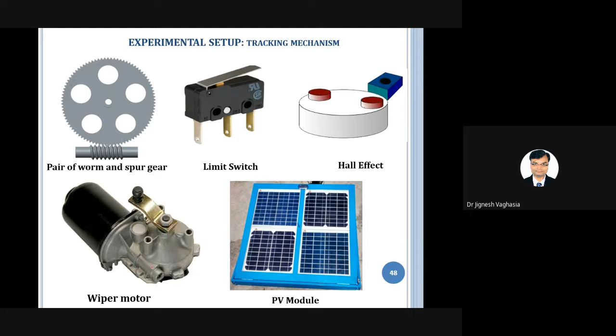Now how will it be rotating? With the help of worm and spur gear, our requirement is 1 degree rotation of the trough at every 4 minutes. So we require a timer, and 1 degree rotation of trough at every 4 minutes. And that's why we have taken a 90:1 spur worm ratio. So in that case, what happened? One rotation of the worm will make one tooth movement. Now one tooth movement is 360 divided by 90. That means one complete revolution of the worm will make a 4 degree rotation of the shaft. So that is more than our requirement.